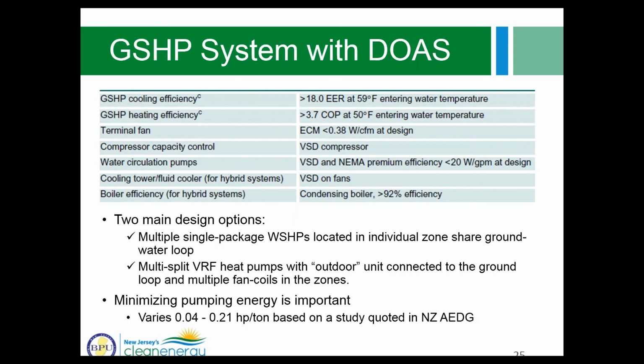the ground loop. So a very important consideration for ground source heat pumps is minimizing pump power. Because with ground source heat pumps, obviously the ground heat exchanger, depending on its design, the pumping energy can be significant. There is a study quoted in Net Zero Advanced Energy Design Guide suggesting that pump power can vary from 0.04 to 0.21 horsepower per ton of cooling capacity. So clearly very wide variations, and recommendation in ASHRAE Net Zero Advanced Energy Design Guide is to shoot for no more than 20 watt per GPM pump power at design conditions.